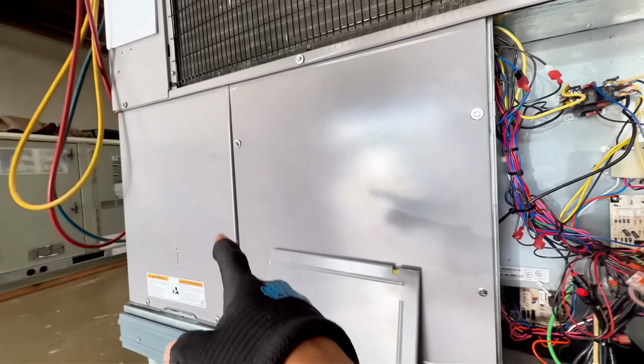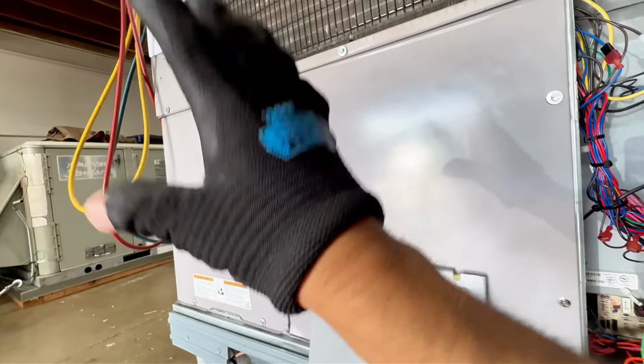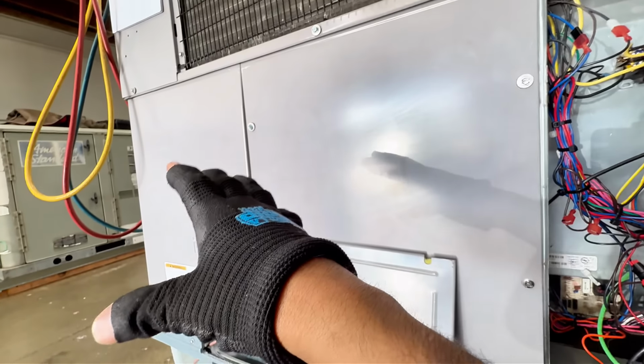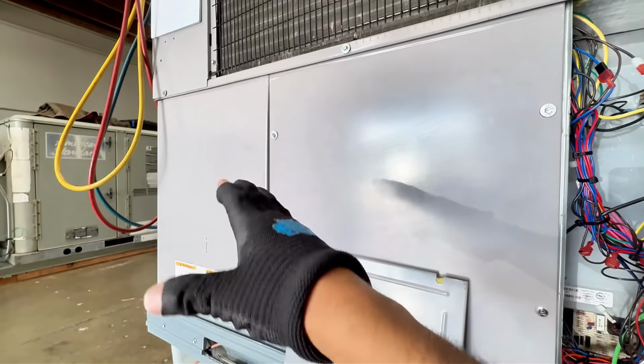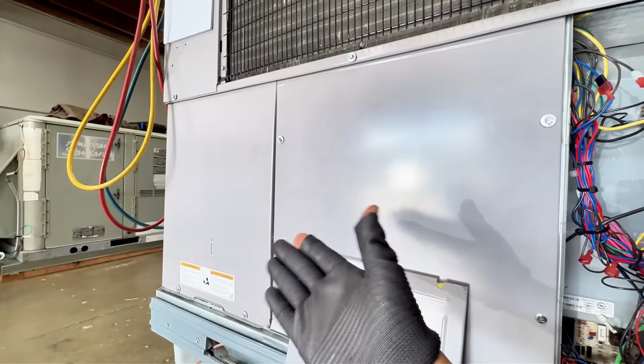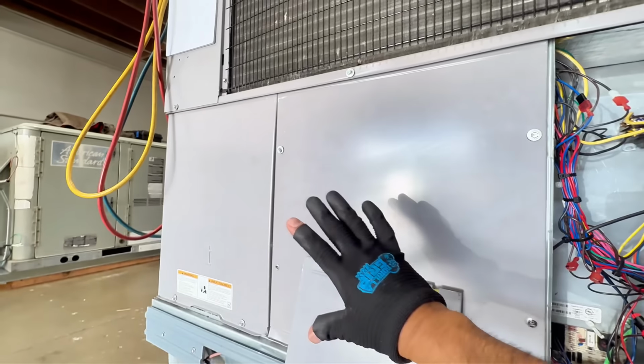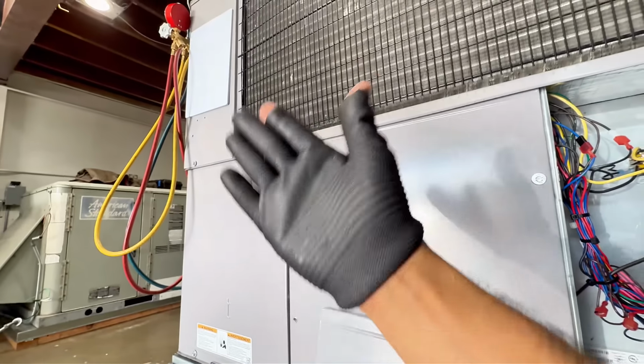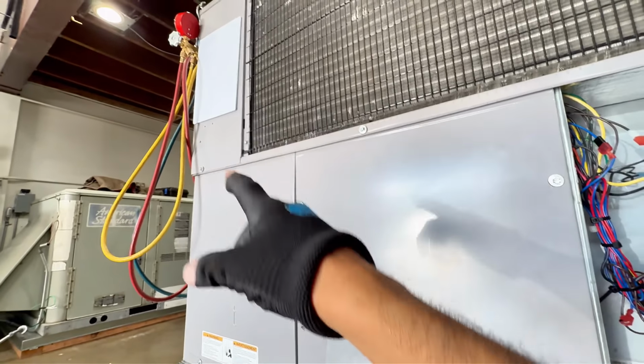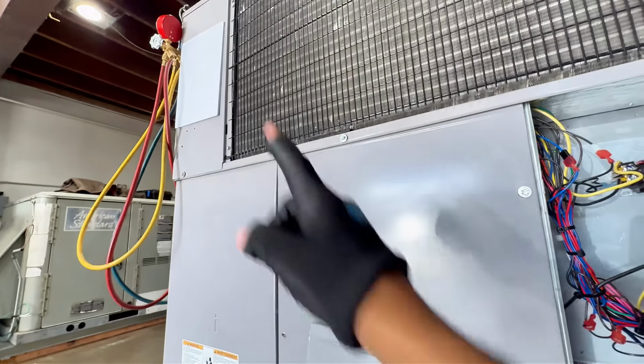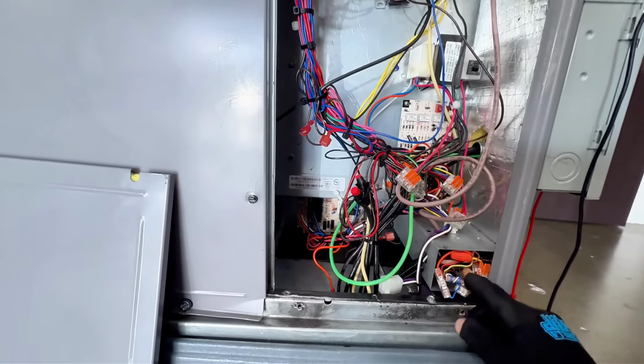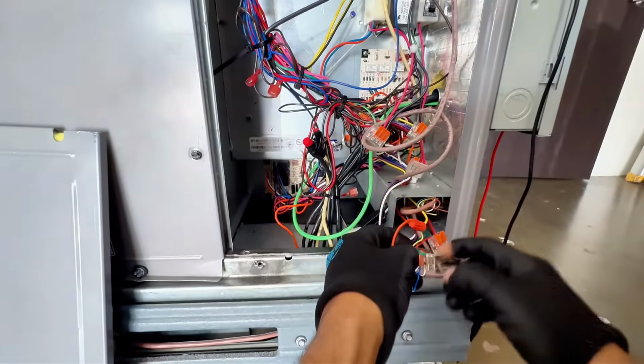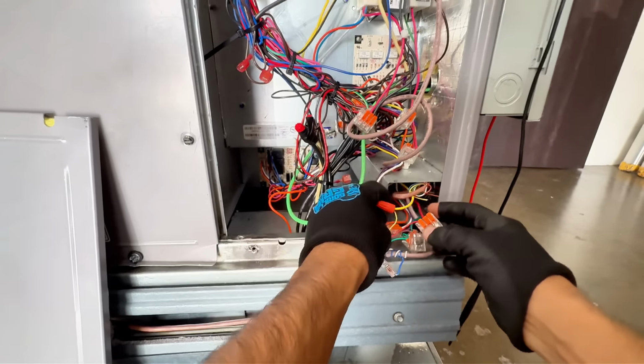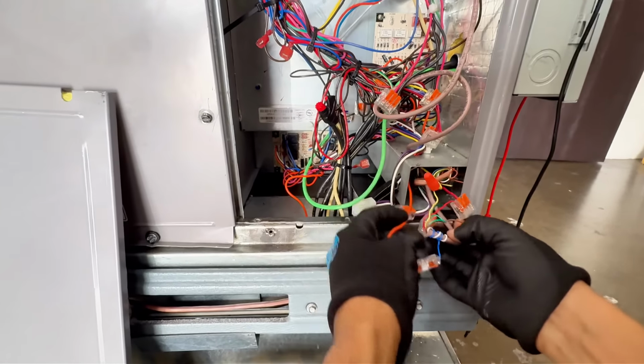I'm also gonna check pressures and superheat and subcool. I think they were doing something with the unit earlier, refrigerant wise, airflow wise. I have no idea. So we can check it right now by checking superheat, subcool, and our pressures. And we're gonna go ahead and write some stuff there too. So first things first, there is a 5-minute delay, right? We did say there's a 5-minute delay.